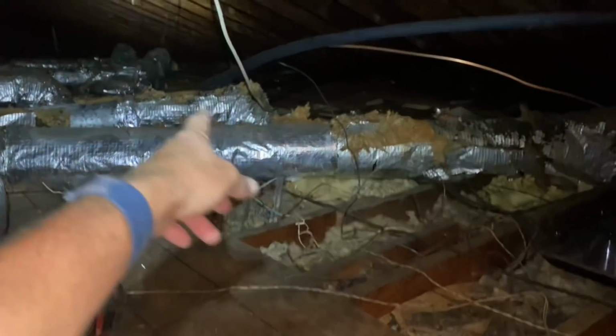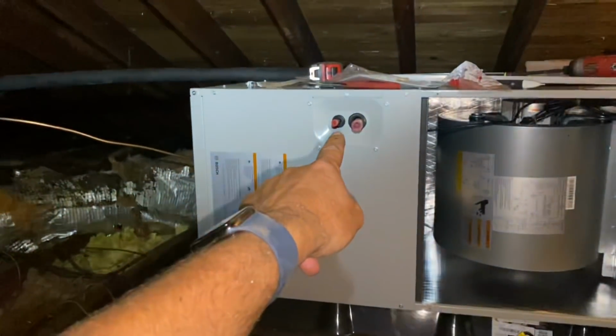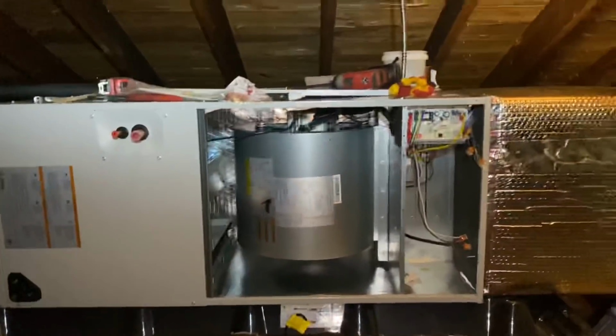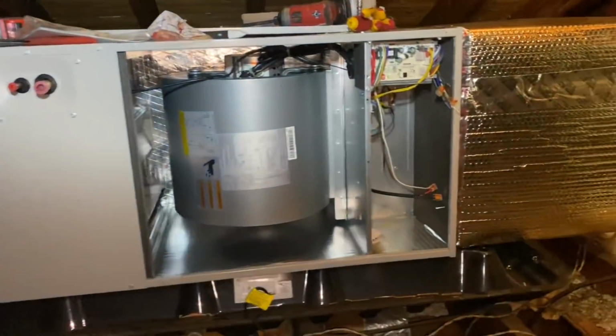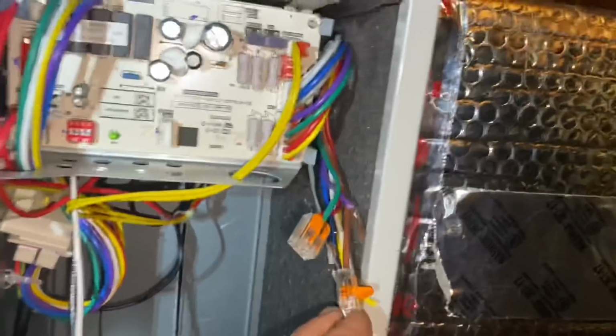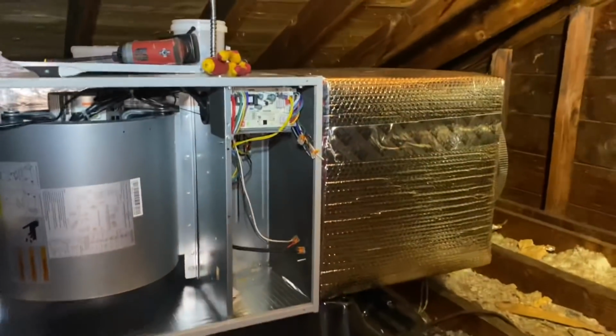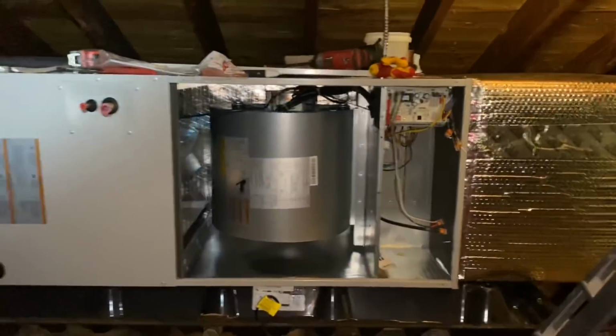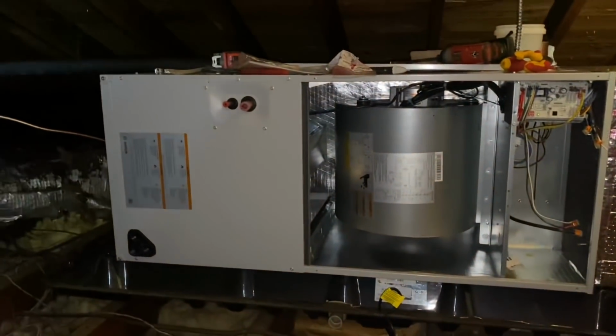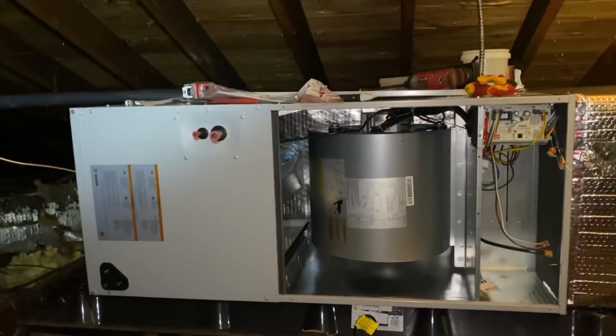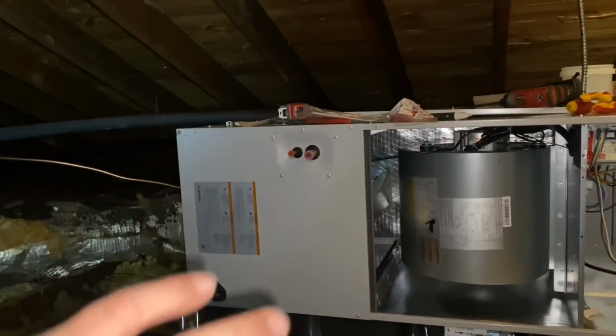Hard to see, but there's my 3/4 by 3/8 line set that Peter is zip tying together. We're going to take some straps and secure it to the roof rafters, bring that down and into the evaporator right there. I already ran my line voltage to the blower, with L1 and L2 connected, common wire-nutted off with the Wago, and I have R and G. It's getting kind of warm up here so we have air blowing, just to get some air moving, because it does feel better than stagnant 90-plus degree air.